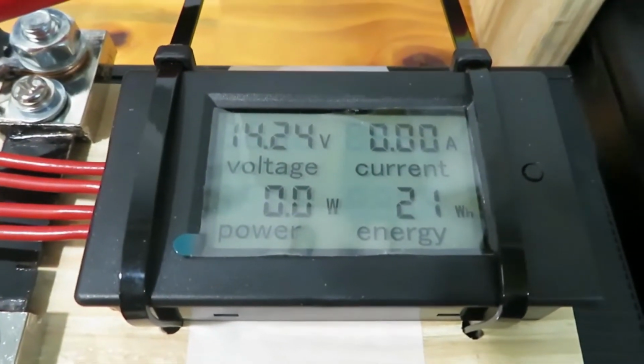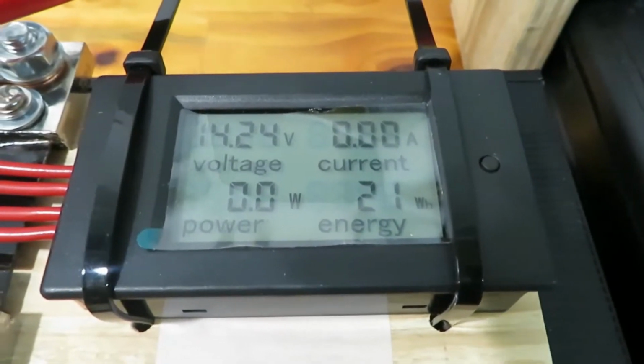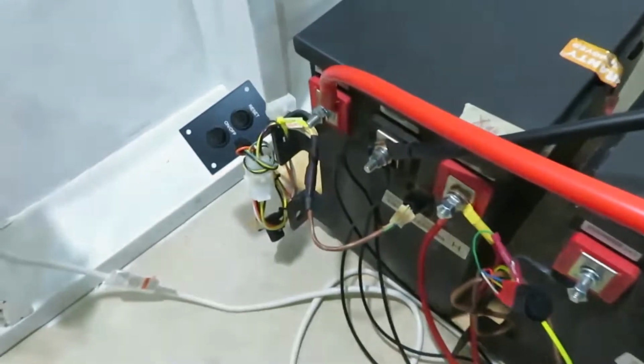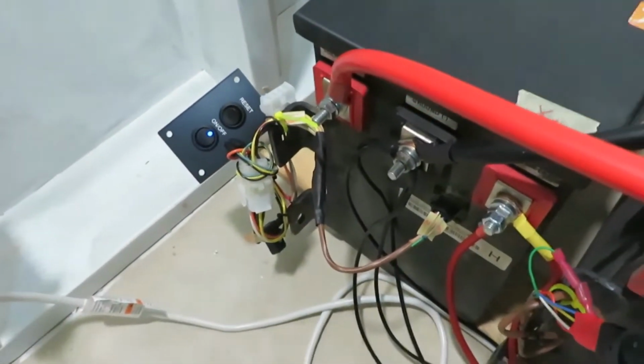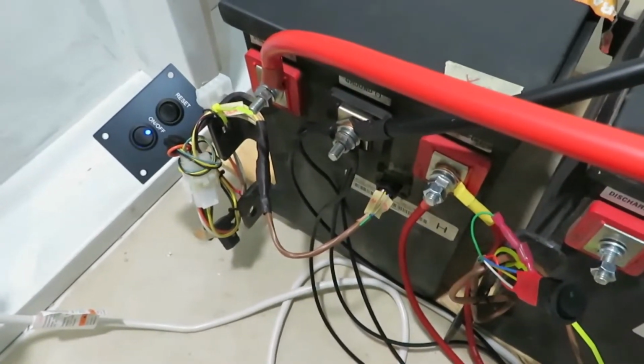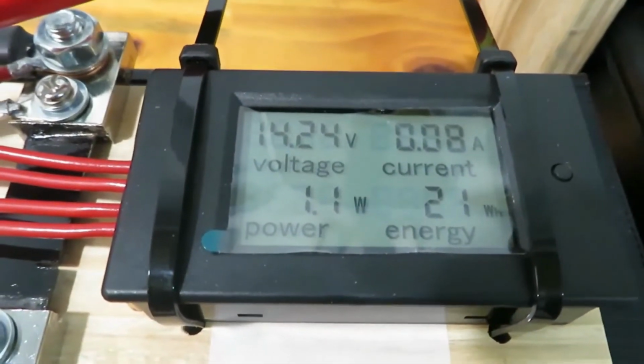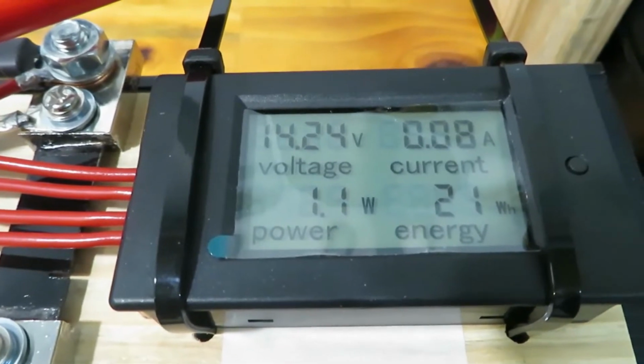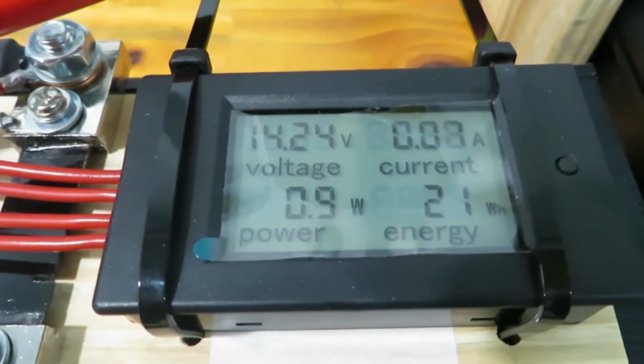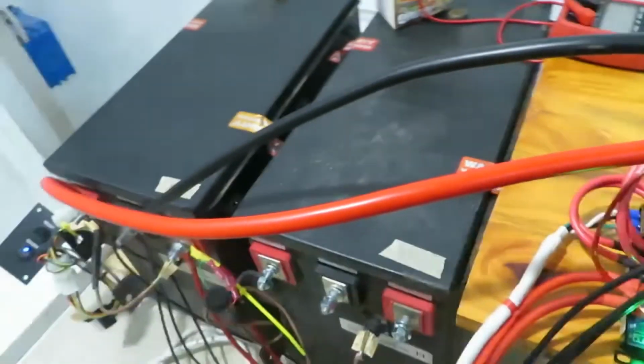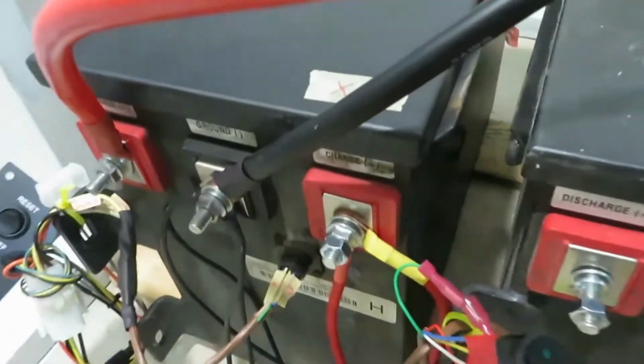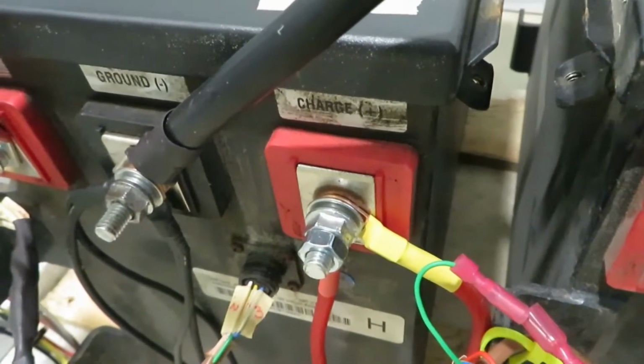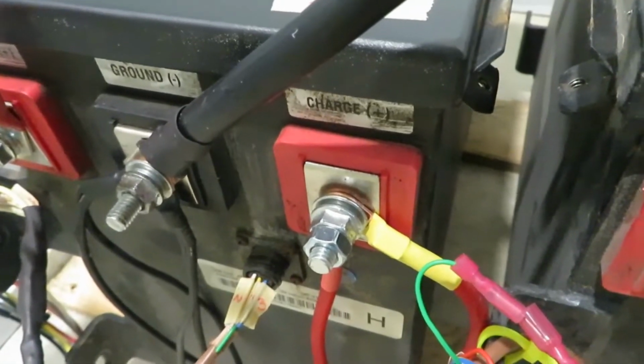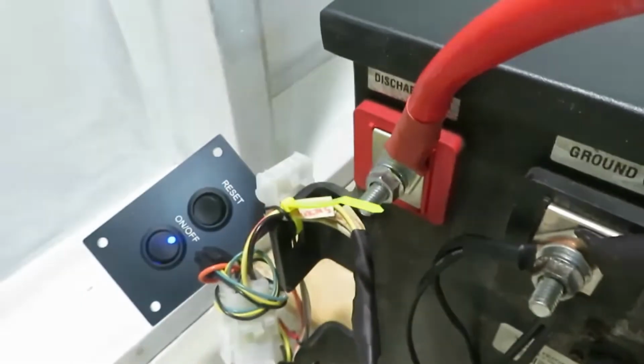Okay, the charger's on, and as you can see, the charger now is producing 14.24 volts. No current yet, so the current is 0. So let's turn on the battery. So we got blue light. Unfortunately, we don't have a clunk. And for some reason, it takes a while for the clunk to start. And now the charger is charging the charge side by 0.07 or 0.08 amps. So after a while, when the capacitance in the charge side is charged up, then we should be able to hear a clunk. And once we hear the clunk, then we know the charge side contactor is closed, and then we could do a reset and close the discharge side.